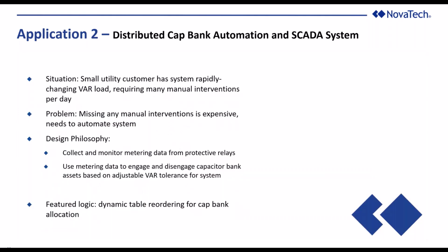Let's show you the list of the criteria here. Over their system, they would have a lot of industrial customers, the machine load of which would dwarf their actual residential load, so they had a power factor problem, and it required constant vigilance, even with SCADA, to bring these things in and out to keep power factor acceptable for their feeding utility.